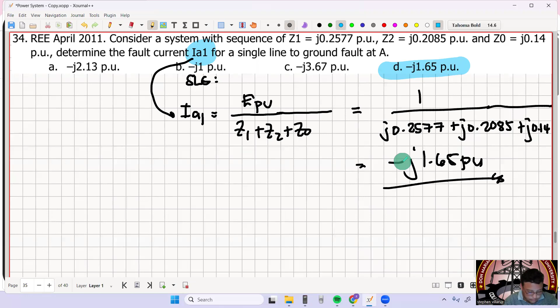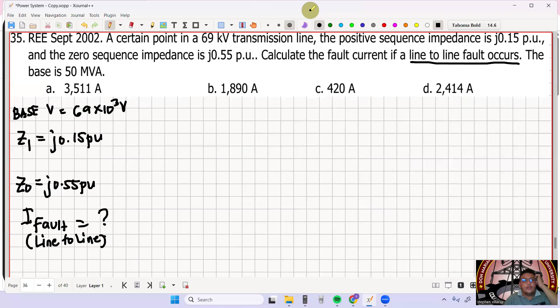Okay, next, number 35. So a certain point in a 69 kV transmission line. So yung ating base voltage natin dito is 69 kV. The positive sequence impedance, so that is Z1, that is j0.15 per unit, and the zero sequence impedance is j0.55 per unit. Calculate the fault current if the line to line fault occurs. Line to line. Okay? So I fault, pero siya ay line to line. So, yan yung tinatanong. Okay? So, given also your base S that is equal to 50 MVA.